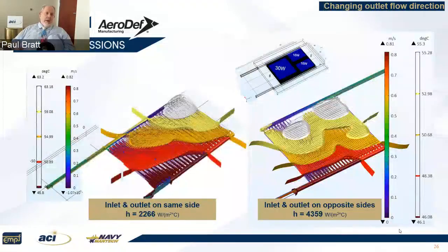Also, by using the multi-physics software, I can investigate just the complete design of this. Here I made a small modification, and just by changing the output of the coolant, instead of having the in and the out on the same side, by having the out exit opposite the input side, I'm able to achieve much better heat transfer coefficients. Next slide.